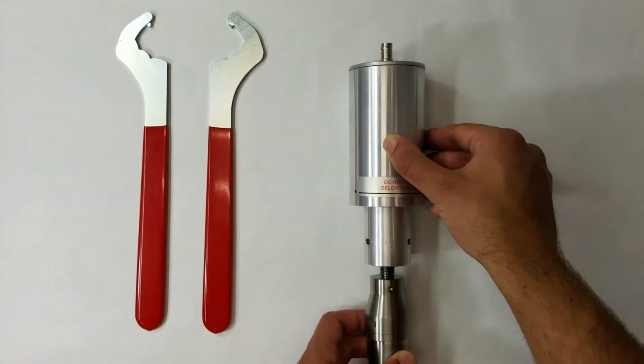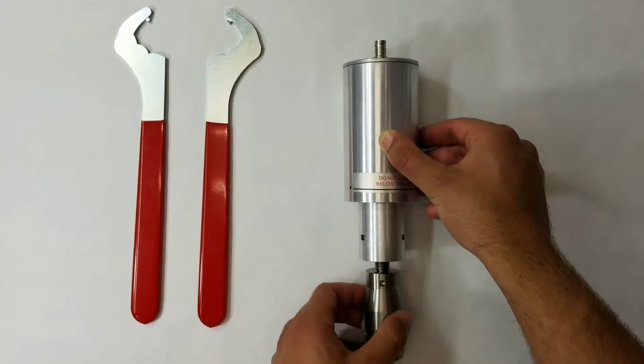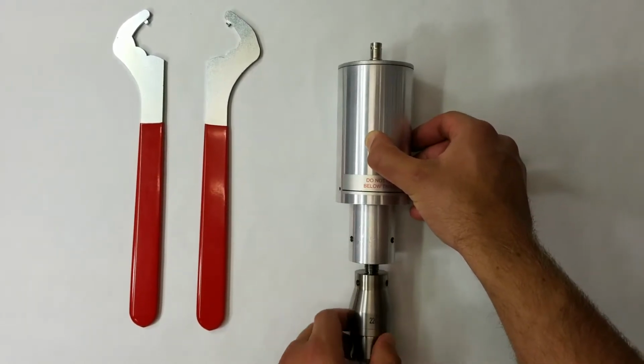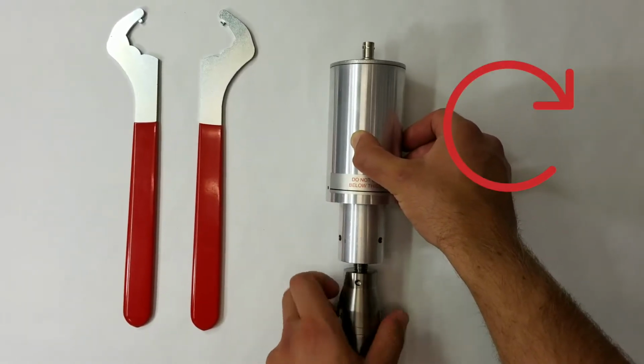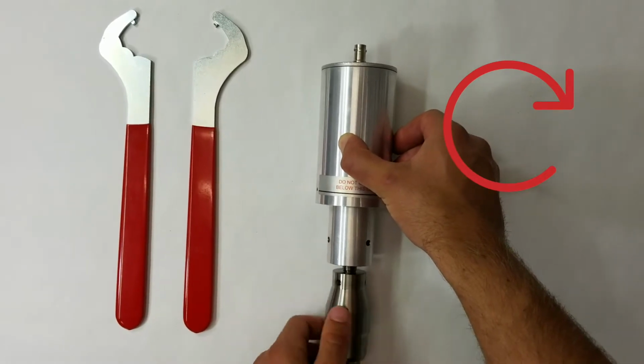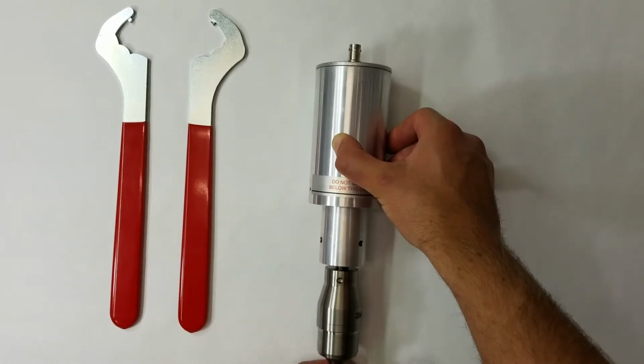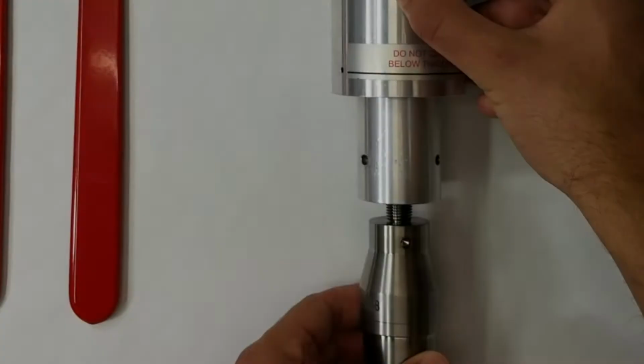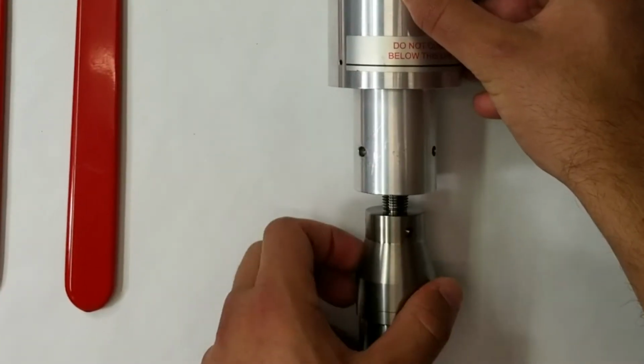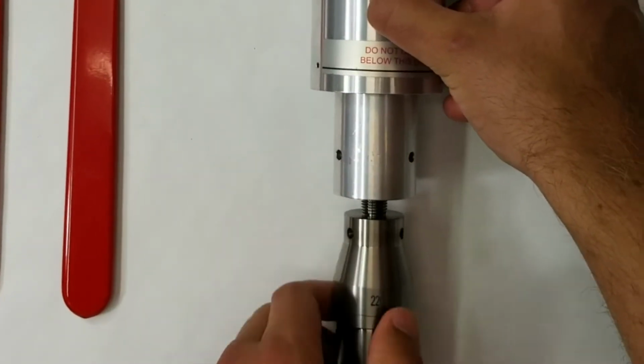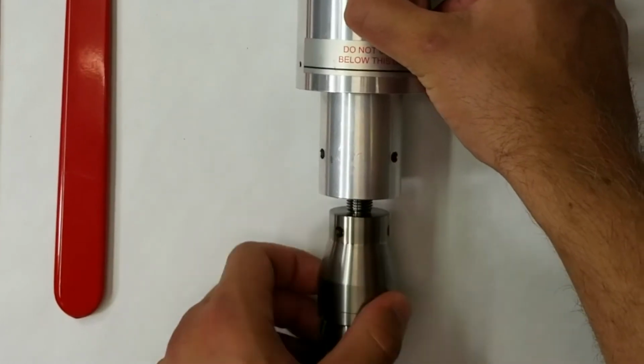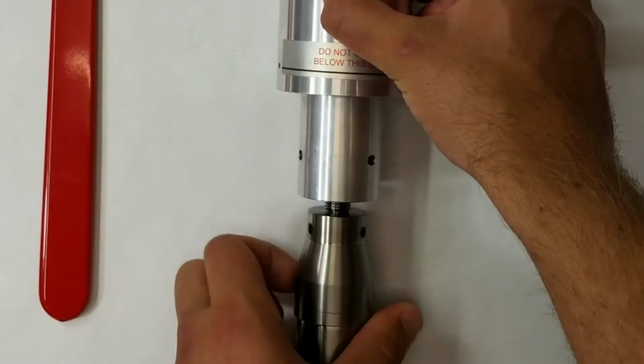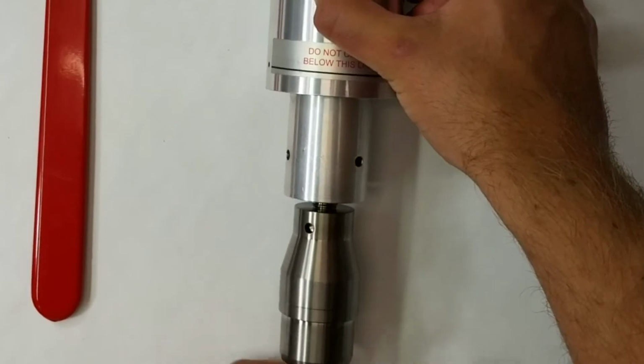To tighten the probe onto the converter, begin by hand threading the probe stud into the threaded hole in the bottom of the converter. Rotate the probe clockwise, righty-tighty, lefty-loosey. The thread should engage easily and spin freely in the threaded hole. No force is necessary. If there is resistance, remove the probe and check the probe stud and the converter hole for debris.